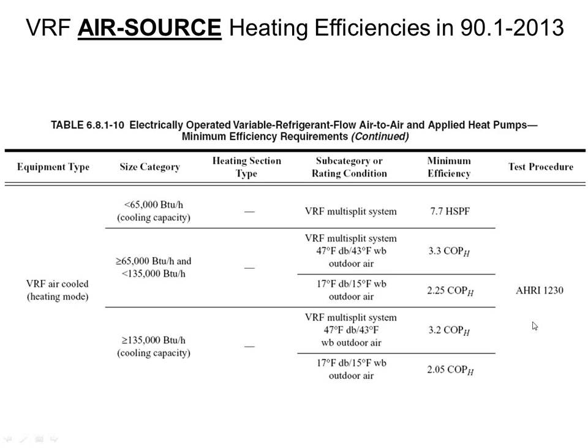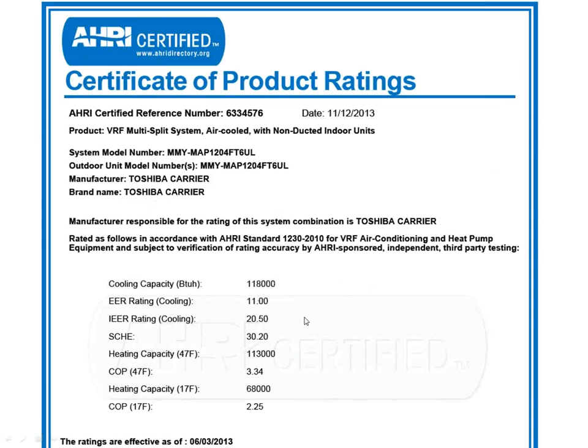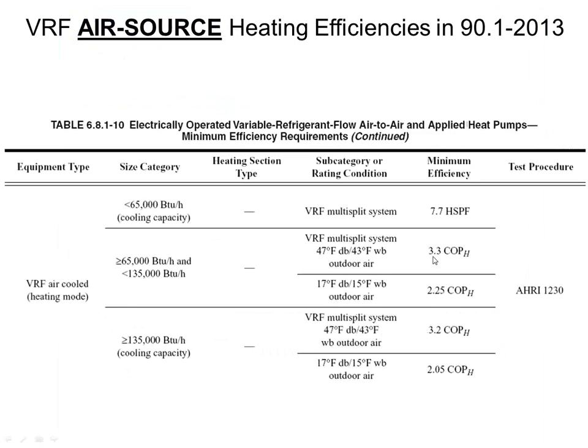That table right there. This is the heating side of the equation, right? So you'll notice for this that we have to meet both the ASHRAE requirement for 47 degrees outside and 17 degrees outside. Each one of them has a COP that we have to hit. 3.3 and 2.25 in this particular case for 118,000 BTU system, which is what we had a minute ago. What were we at on that one I grabbed? We were at 2.25 and 3.34. So we hit the bare minimum on the 17 degree number, and we slightly exceeded the 47 degree number.